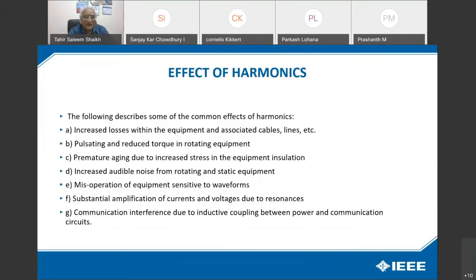The following are some of the common effects of harmonics: increased losses, pulsating and reduced torque in motors and rotating equipment, premature aging due to increased stress in the equipment, increased audible noise from rotating and static equipment, misoperation of equipment sensitive to waveforms, substantial amplification of current and voltage due to resonance, and communication interference due to inductive coupling between power and communication circuits. I have so many examples in my country where these phenomena happen.